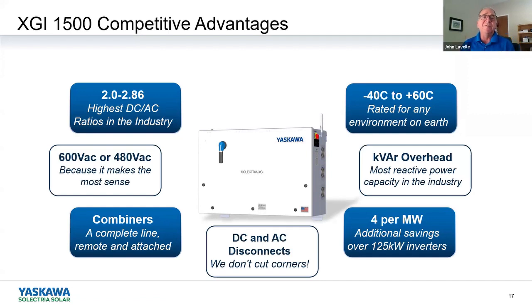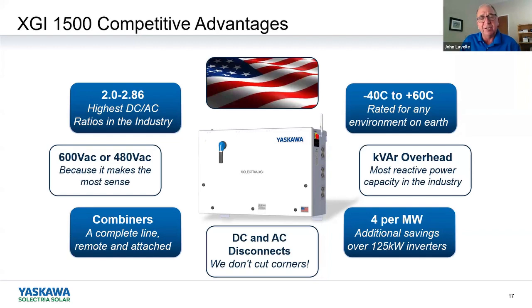We also, all these inverters have integrated AC and DC disconnects. There's a couple of our competitors that do not have these integrated disconnects, and what that means is that you have to get an external box that sits next to the inverter to meet the code, and that adds to installation costs and adds more hardware to the installation. So with the Yaskawa machines, you have integrated DC and AC disconnects. So I think that that's the last slide.